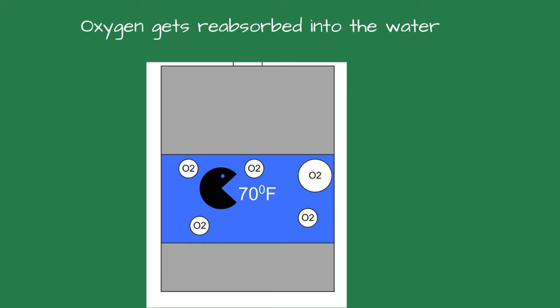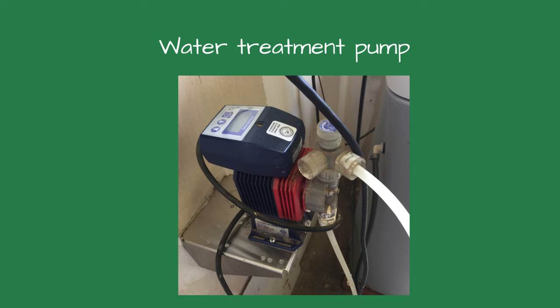The water will reabsorb the oxygen molecules and they will attack the metal surfaces inside the boiler with a vengeance. Dissolved oxygen is 10 times more corrosive than carbon dioxide, which forms carbonic acid when mixed with water. Oxygen corrosion is twice as corrosive at 122 degrees than it is at 86 degrees. You have to either keep the boiler warm or use a chemical treatment program which includes an oxygen scavenger. The oxygen scavenger consumes the oxygen so it won't attack the metal, ensuring the longevity and efficiency of the system.